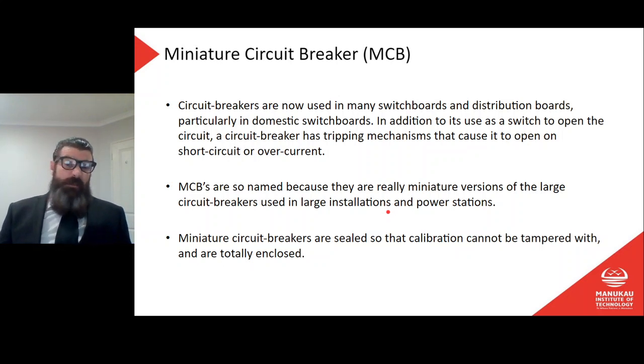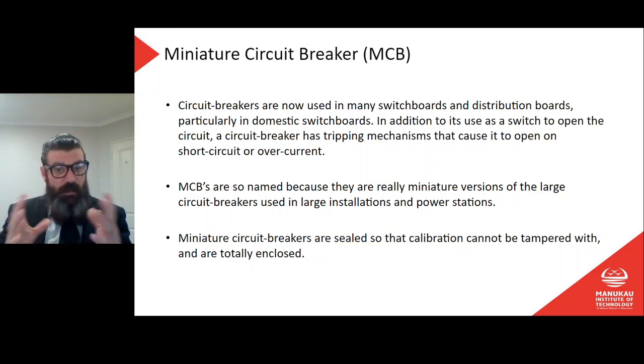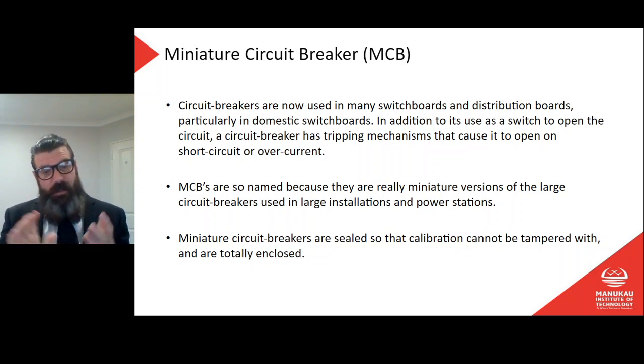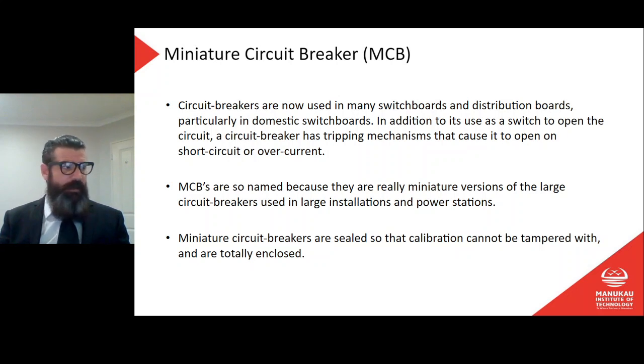Circuit breakers are now used in many switchboards and distribution boards, particularly in domestic switchboards. In addition to its uses as a switch to open the circuit, a circuit breaker has tripping mechanisms that cause it to open on short circuit and overcurrent. MCBs are so named because they are relatively miniature versions of the large circuit breakers used in large installations and power stations. Miniature circuit breakers are sealed so that the calibration cannot be tampered with and are totally enclosed.